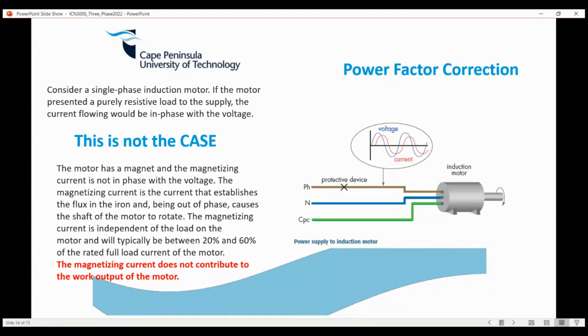They're saying the magnetizing current is independent of the load. We're aware of that since S has two components, P and Q, and Q is like the foam on the beer or the air in the Lay's packet of chips. Typically the magnetizing current will be between 20 to 60% of the rated full current, so we don't actually use all the current - a certain amount is lost to the magnetizing current, which is used for the magnetic field. Lastly, they state the magnetizing current, or reactive power, does not contribute to the work output of the motor.